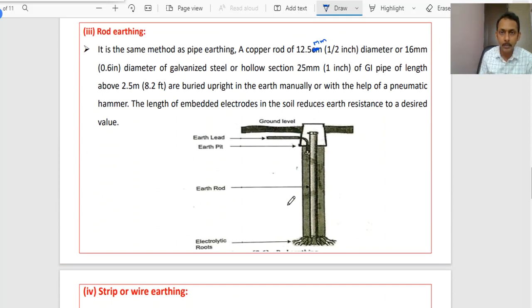It is also the same method as pipe earthing, but a copper rod of 12.5 mm, which is nothing but half-inch diameter, or 16 mm diameter of galvanized steel, in the sense some 0.6 inch diameter of galvanized steel, or a hollow section of 25 mm, nearly 1 inch of GI pipe, of length above 2.5 meters will be buried upright in the earth manually or with the help of some pneumatic hammer.